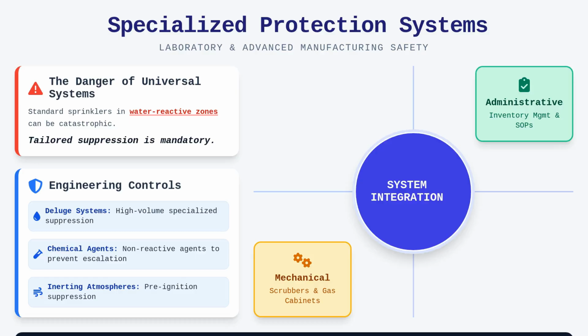Instead, we utilize fire protection methods that align with the specific hazard class, often incorporating inerting atmospheres that actively suppress the combustion environment before an ignition source can reach the activation threshold. The administrative controls, such as strict inventory management and established standard operating procedures for handling, are just as vital as the mechanical ones. Without rigorous administrative oversight, the best engineered scrubber or gas cabinet remains vulnerable to human error, which is often the precursor to significant release incidents.